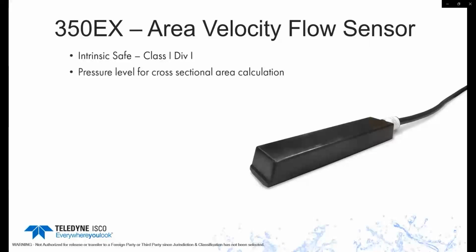What we do with our sensor is we do a level calculation using a pressure sensor built into it. And that's going to measure the depth. Once we know the depth and the diameter or the pipe dimensions, we can calculate the cross-sectional area. There are other manufacturers out there, and we can do it as well, that use maybe an ultrasonic as their primary level measurement. We can do ultrasonic for level as well. So you just kind of have to pick and choose what is going to be the best for your application. We use an ultrasonic Doppler sensor, a couple crystals in the nose of that. One's transmitting, the other one's receiving. Again, everybody does something very similar. There's typically two crystals in about anybody's continuous wave Doppler sensor that you'll find in the market.